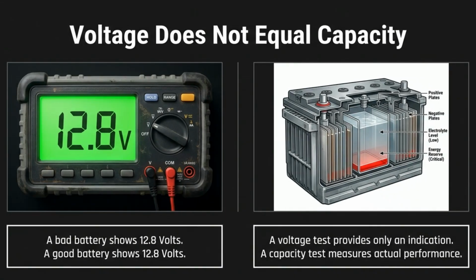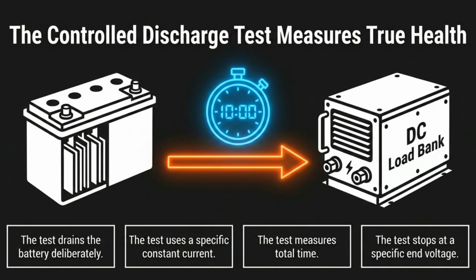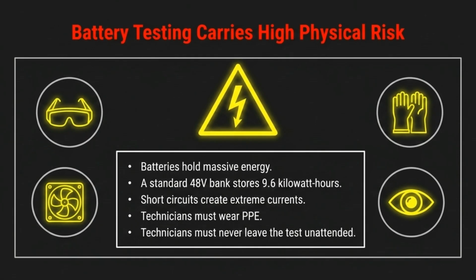While a good and a bad battery might both show 12.8 volts at rest, only a capacity test measures actual performance. The controlled discharge test reveals the true health of a battery. This process deliberately drains the battery at a specific constant current while monitoring the time taken to reach a designated end voltage. Battery testing carries high physical risk.